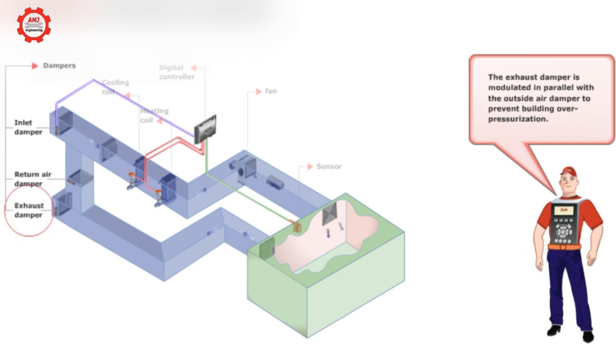The exhaust damper is modulated in parallel with the outside air damper to prevent building over pressurization.